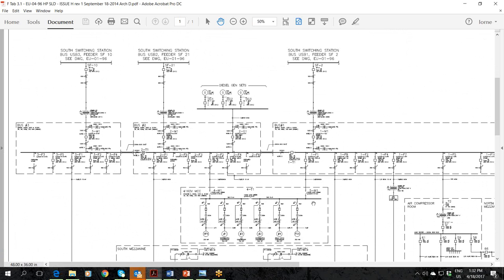Today we operate with the ties closed and only one source that's active, with the other feeder breakers, the other main breakers, I should say, open. The only reason we're doing that is the diesel generator control setup was designed for a supply with an alternate. It wasn't designed for this third, so we're basically waiting for funding to replace the controls associated with this, at which time we'll go to a ties open system for the heating plant as well. But these do provide black start capability.